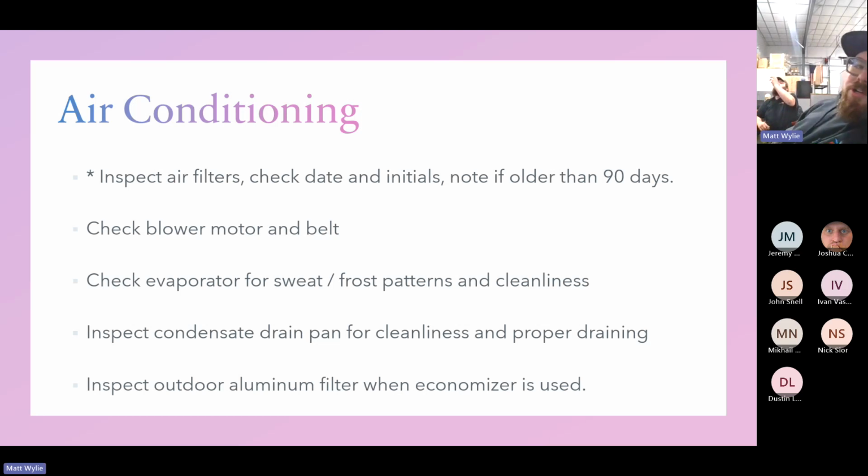So back to that, Josh, how many of us, when we do a maintenance, actually look at that? When we pull something, none of us change the belts, do we actually look at that? I bet there's a lot of stuff that's terrible. Yeah, I mean that's just one of those things because you've got to turn it off to change the belt, or even just to look at the belt to see if it's cracked. But yeah, just glancing at it, if it looks dirty, then it is dirty. Yep. But literally, you should just see the metal when you look at it. That color's the metal. It isn't brown.